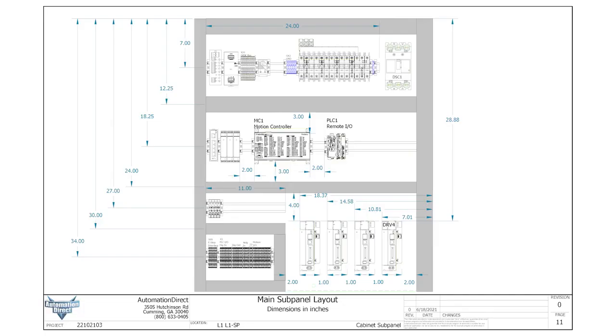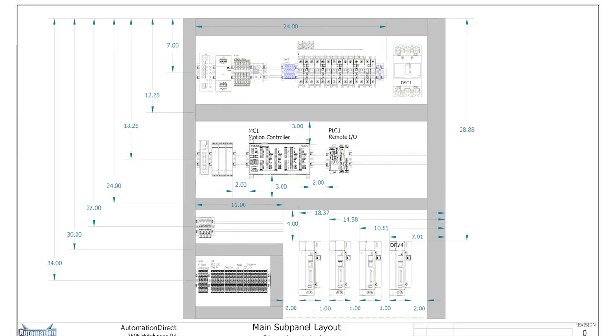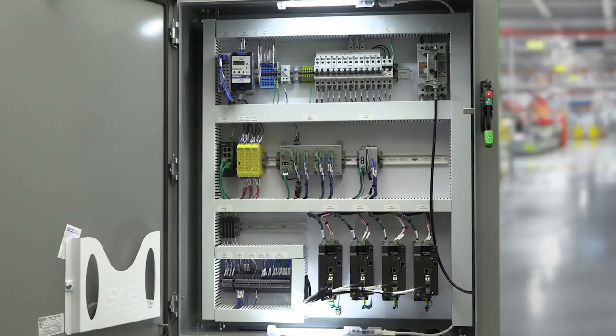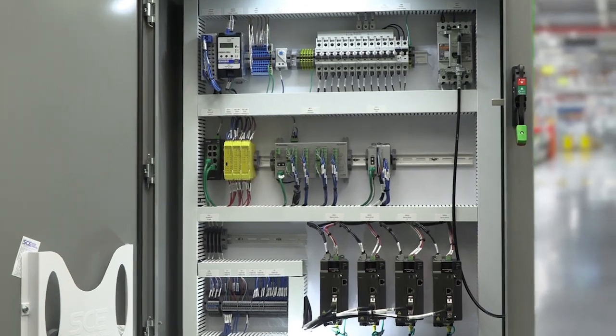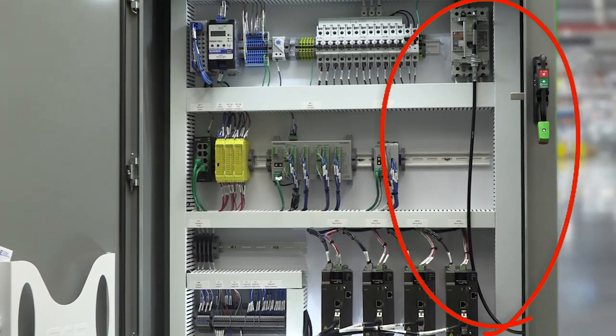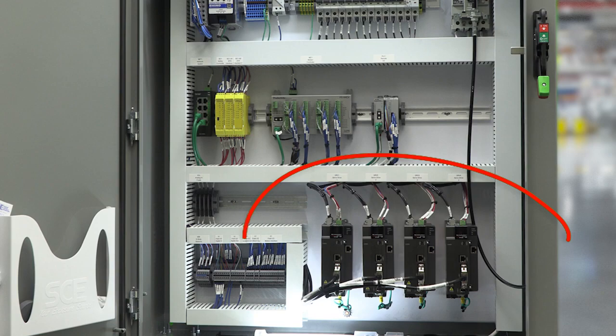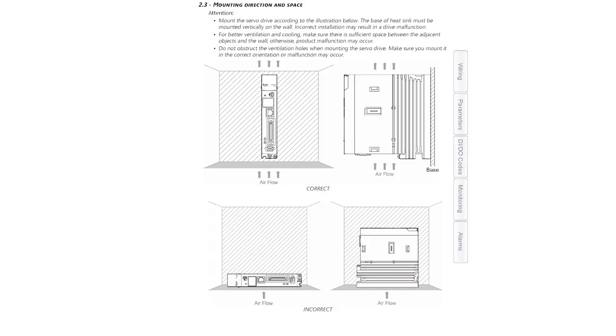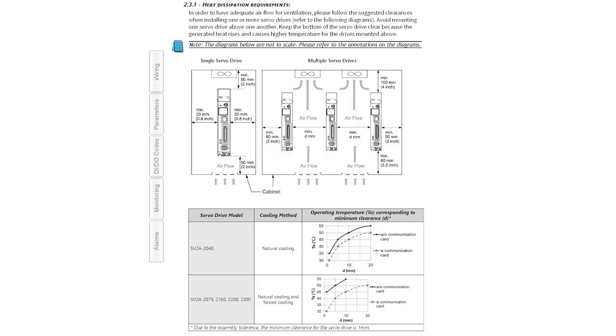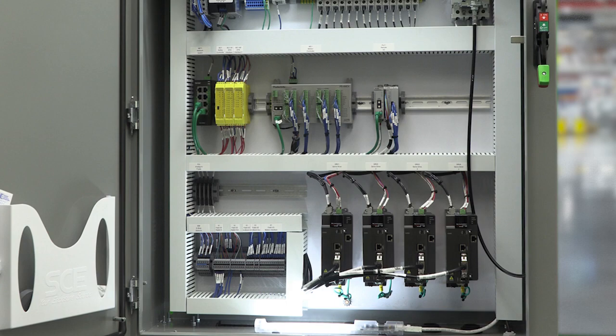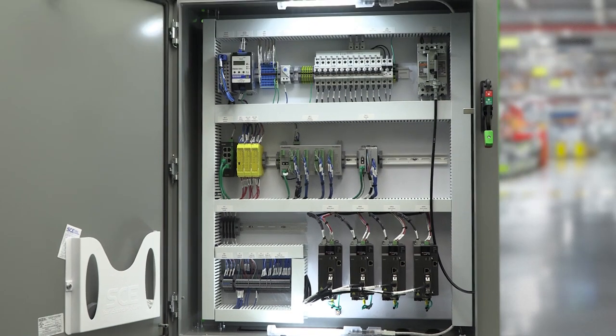With that said, we've chosen this layout with a few things in mind. 3-phase power comes in on the right, into the main disconnect, and back into the AC circuit breakers in the top row. The right side was chosen for the main disconnect since this cabinet has a cable-driven handle that mounts on the right side. The servo drive gets the bottom row for 2 reasons. First, this allows heat to rise away from the servo drives, and second, if we bring the servo cables in from the bottom of the cabinet, we don't have to worry about voltage separation for the servos.